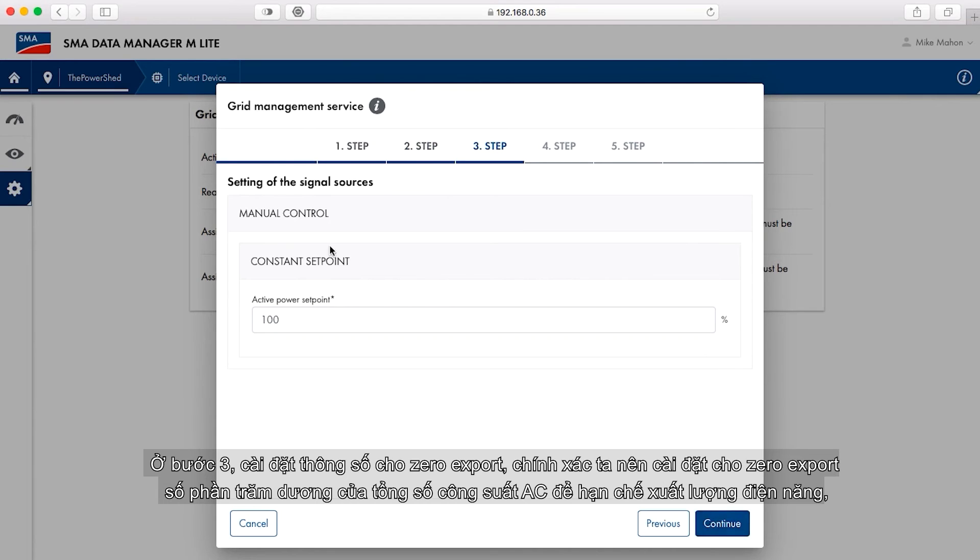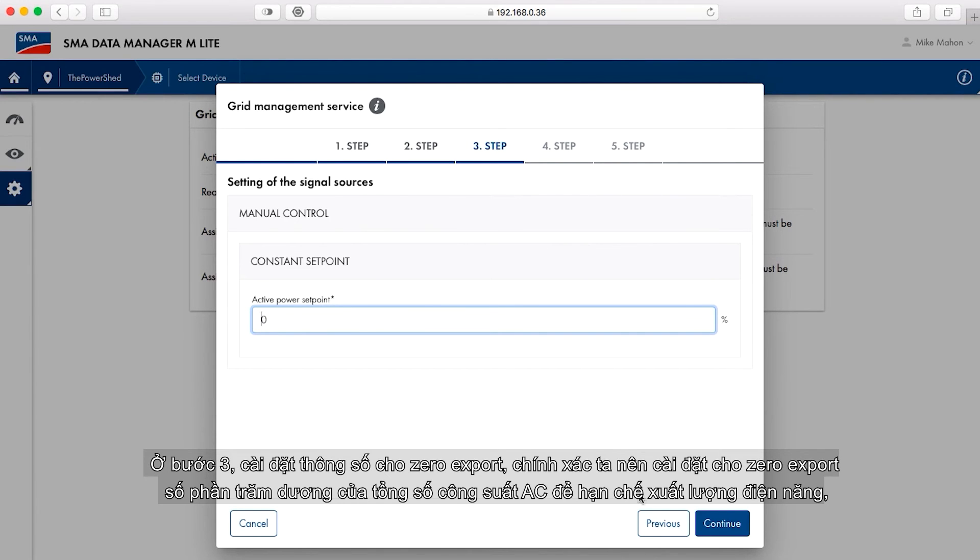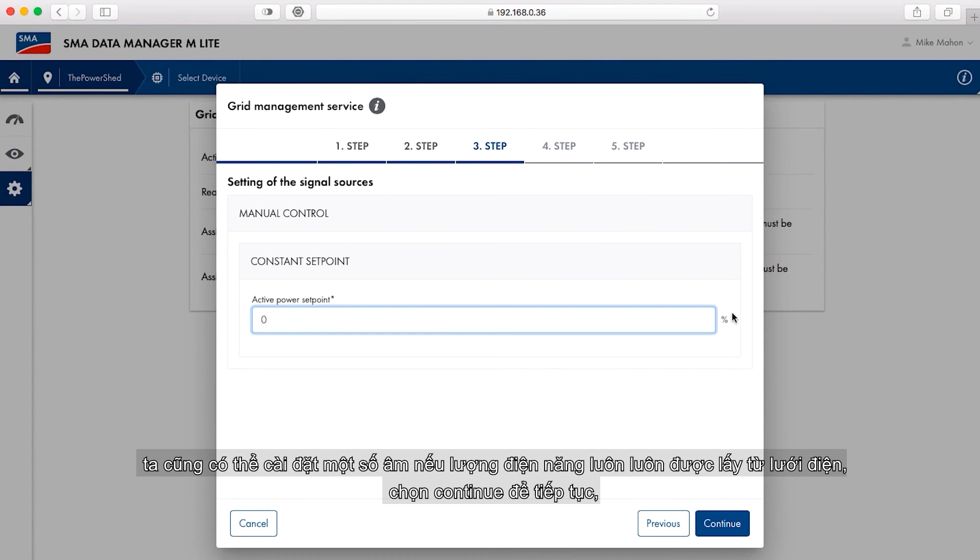In step three, set the set point for export. Zero is correct for zero export. A positive percentage of total AC power should be selected for export limitation. A negative number can be set if net power should always be drawn from the grid. Select continue when done.